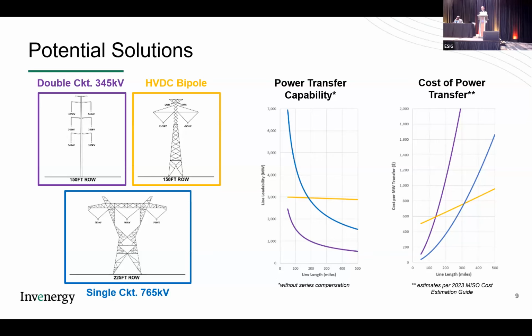What you see is in short distances, often the AC solution is great. On the right is the power transfer capability as the line length increases, and further right, the cost of that power transfer capability as line length increases. That chart includes the converter station, substation cost, and line cost. For short distances, the AC solutions are great.